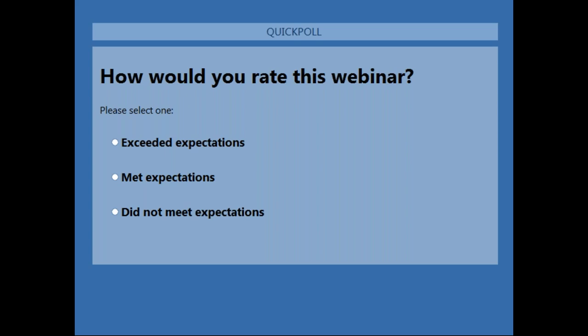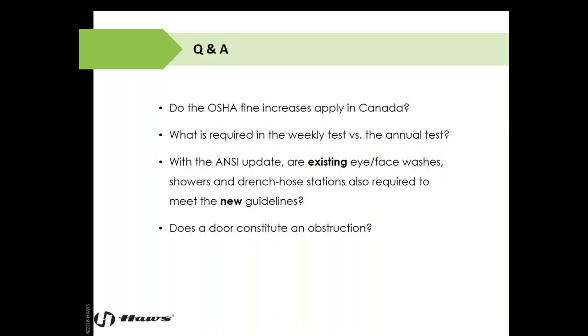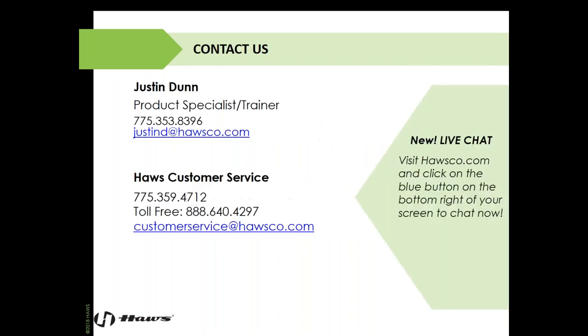The ANSI standard gives us the definition of flushing fluid as potable water or medically treated water, like saline solution. Either one of those are perfectly acceptable. Self-contained equipment is really the answer to that, whether it be a portable, if it's just airborne contaminants, or Haws integrated, these big yellow booths, if it's something more severe. So that's really the way to go, self-contained, and it'll be compliant with your needs.